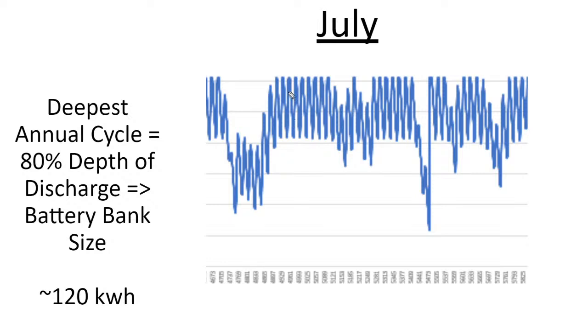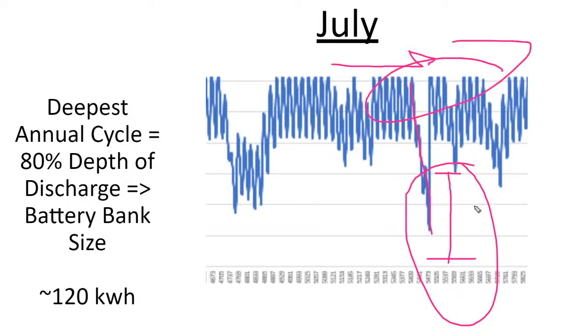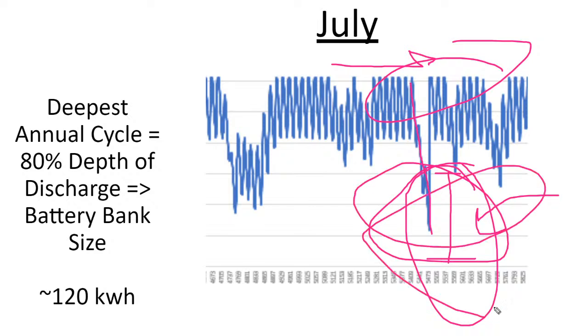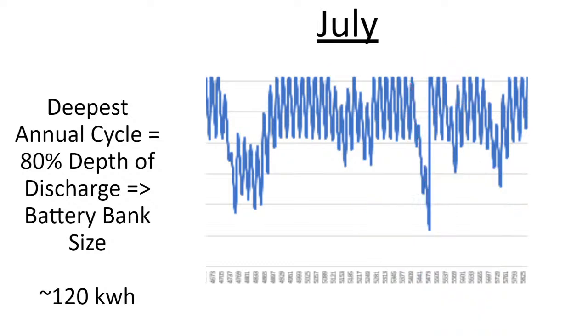The degradation on that cathode and anode really has to do with two things. One, just the duration of the discharge, and two, the relative storage capacity that's left in the battery, because that's kind of the same thing as having a battery that's just half as large as the larger battery. If you have the same load on the battery and it is discharging a battery that's half the size, that's going to be even harder on the battery than if it was getting a gentler rate of discharge. So it shouldn't surprise you that more damage occurs towards the bottom of the battery when you're operating at a low capacity versus a high capacity.